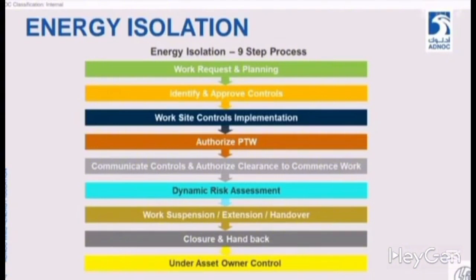The next step we have is closure and handback. When we have finished working on our equipment, it is our responsibility to de-isolate it as per the blind list, tag list and all the information we have isolated. After de-isolating it, our JP will re-ensure it, then our permit issuer PI will re-ensure it, then our ICC, Isolation Confirmation Certificate, will be closed, and with that we can hand over the handback.